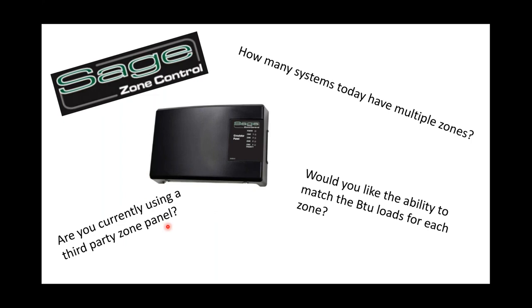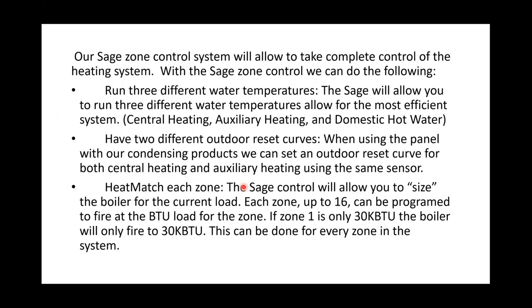And again, it's going to be almost identical in price to a Taco panel. So if you're already using one and you're using our boiler, this is going to be a great add-on for you. It allows you to take complete control of that heating system. We can dial in every single zone as far as the BTU rates.